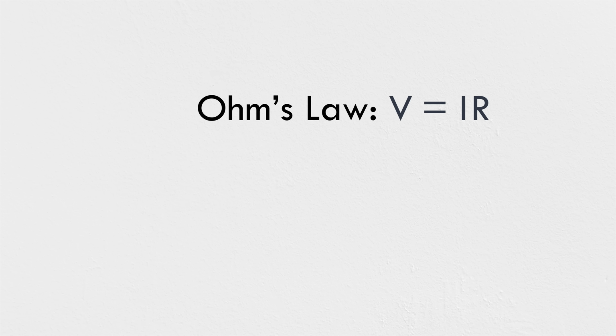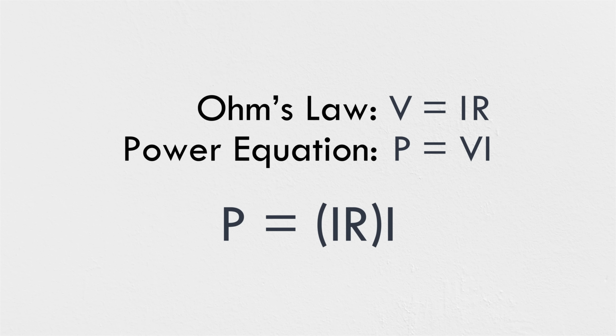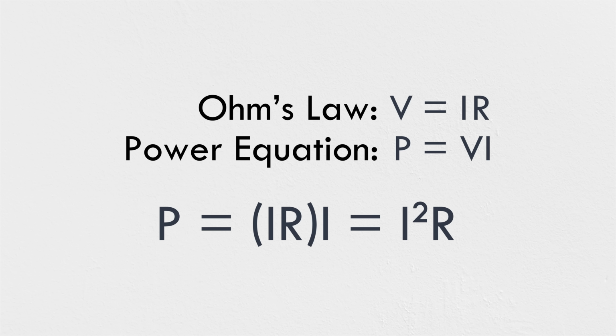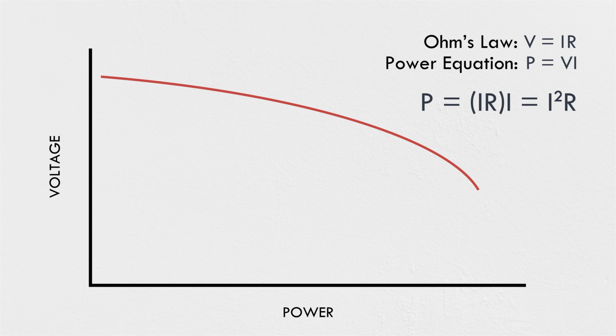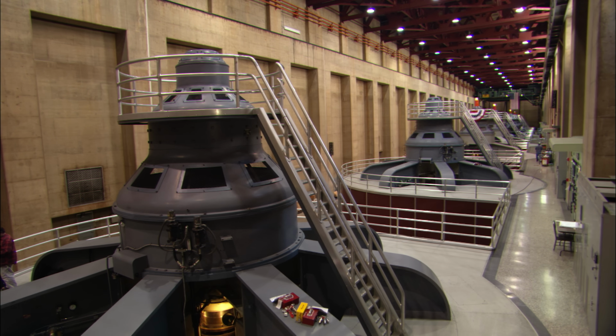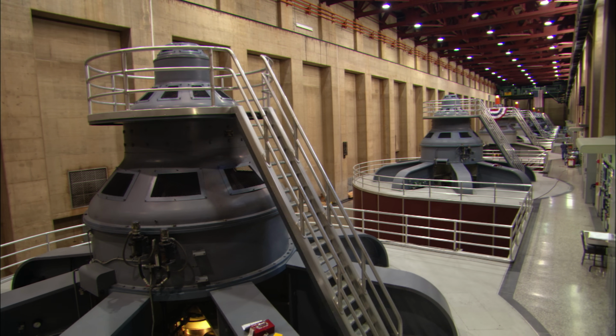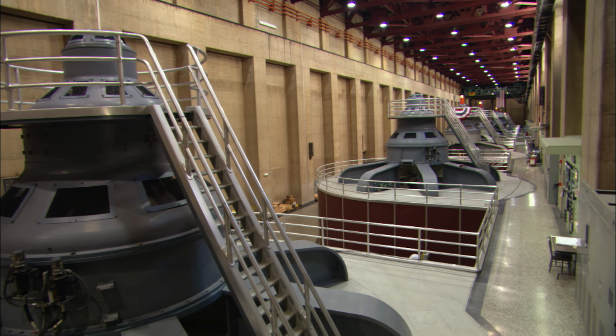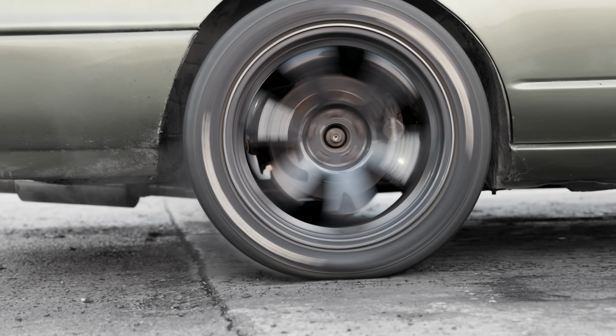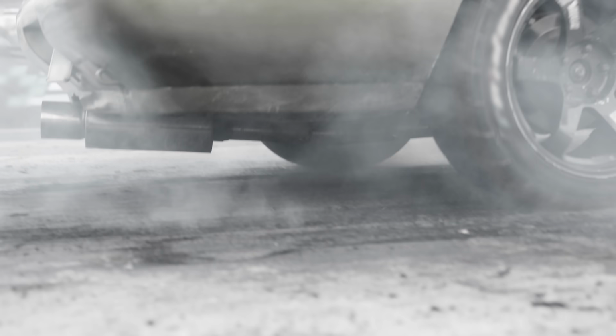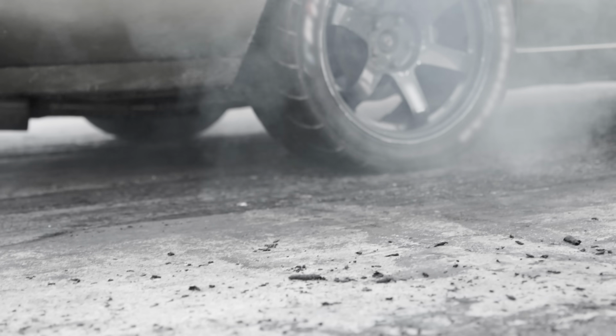If you combine Ohm's law and the power equation, you can see that the power lost on a transmission line is related to the current squared. Double the amps, quadruple the power lost as heat. But the further along this curve that the system operates, the more dangerous things get. There is a point, the nose of the curve, beyond which greater demand on the system actually reduces the amount of power that can be delivered, all while the voltage continues dropping. The generators may have the capacity to supply more power, but it can't reach the load because of the limitations of the system. Operating below the nose is unstable because generators lose control of their speed, like a rubber tire losing its grip on the road.